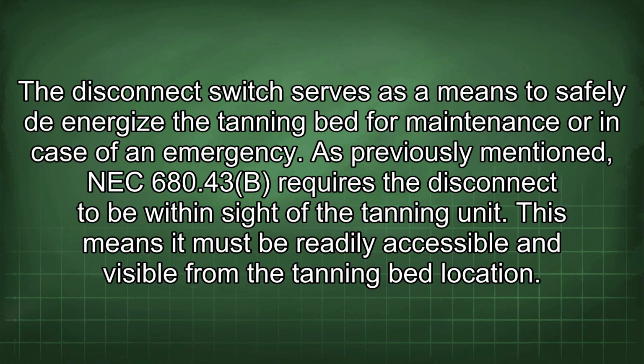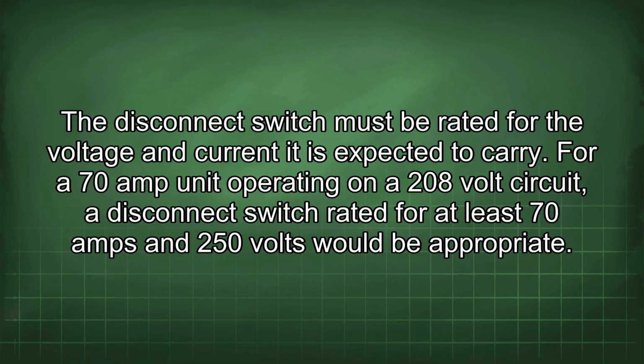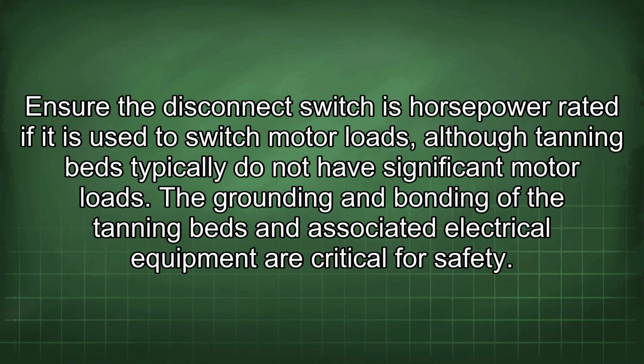The disconnect switch serves as a means to safely de-energize the tanning bed for maintenance or in case of an emergency. As previously mentioned, NEC 680.43b requires the disconnect to be within sight of the tanning unit. This means it must be readily accessible and visible from the tanning bed location. The disconnect switch must be rated for the voltage and current it is expected to carry. For a 70 amp unit operating on a 208 volt circuit, a disconnect switch rated for at least 70 amps and 250 volts would be appropriate. Ensure the disconnect switch is horsepower rated if it is used to switch motor loads, although tanning beds typically do not have significant motor loads.